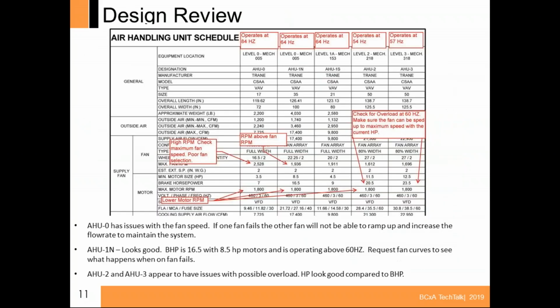This here is on the design review, and this is the current project I have right now. Looking at it, it looks like everything is done by the vendor. The vendor put all this stuff together, particularly when it has 119.62 inches. You know, does that really make a difference? Or, you know, max, there's crazy numbers in there for some reason. But if you look at air handler AHU-0, I wrote on the bottom right that the fan is at 16.5, and there are two of them, and the speed is 2,528 RPM.